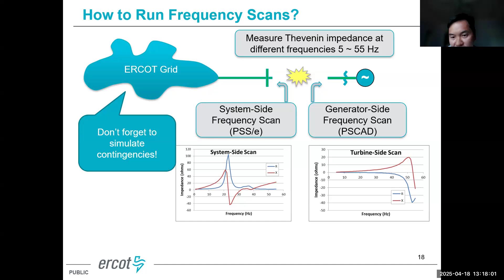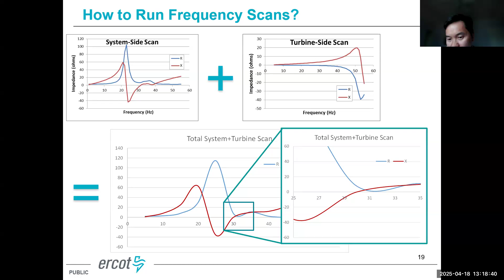After we have the total impedance, we look at R and X. Basically, we look at the reactance X crossing from negative to positive. In this example, X crosses 0 at 30 Hertz. Then we look at the resistance at the crossover frequency, 30 Hertz in this example. If R is positive, that means no SSCI issues. If it's negative, then there are SSCI issues.